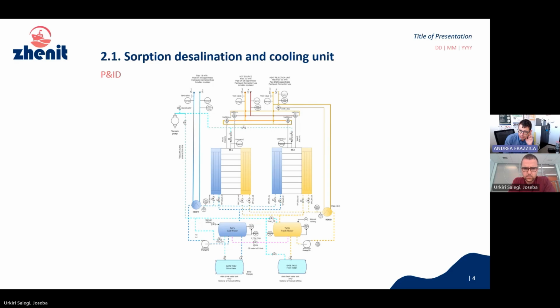The process is driven by the waste heat coming from this hot source on top of the picture, while at the bottom we have these two tanks, the blue and yellow one, that are containing the salted water and the fresh water respectively. So what happens is that when we start the adsorption process, the salted water is sent to the adsorber. It evaporates inside the adsorber, and so of course the salt remains on the evaporator side, while the fresh water is shifted to the condenser side.